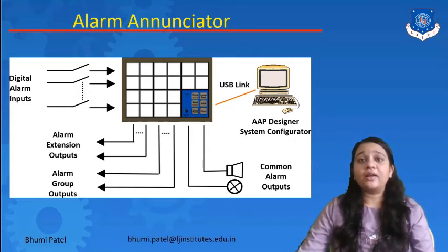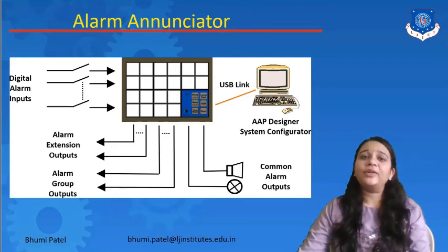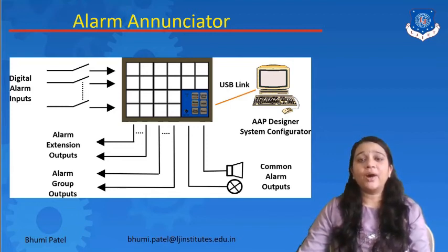So if you connect a bulb in series with this coil, it glows if and only if the coil is energized and healthy. In this way, for 50 such coils you need to use 50 bulbs, each connected in series with an individual coil, through which you can monitor the process of the system by the glowing of the bulb. This is the basic and easiest model for monitoring purposes. So the alarm annunciator is the centralized model which gives an audio-visual signal for the fault process.